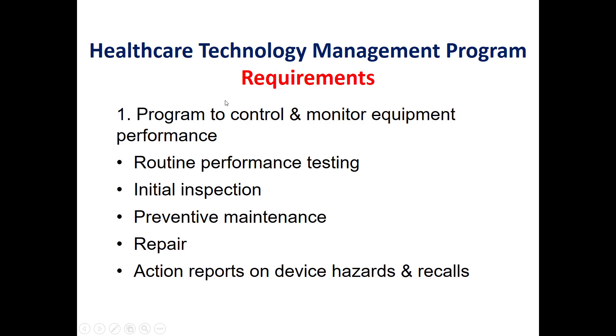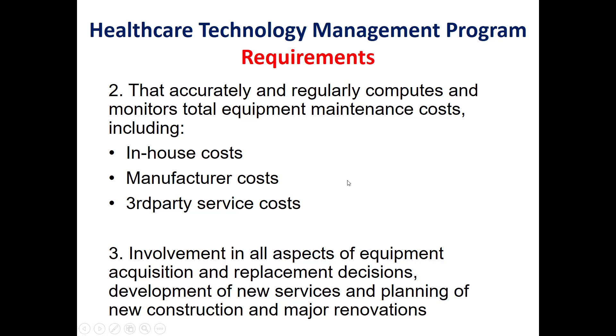Now we will talk about the requirements for such a program. First, the program has to control and monitor equipment performance through routine performance testing, initial inspection of new equipment, preventive maintenance, repair, and action reports on device hazards and recalls. The second requirement is to accurately and regularly compute and monitor the total equipment maintenance cost, both in-house and out-house — meaning manufacturer or third-party services.